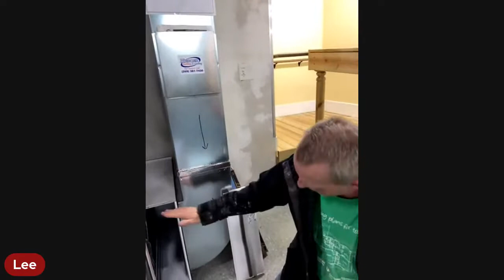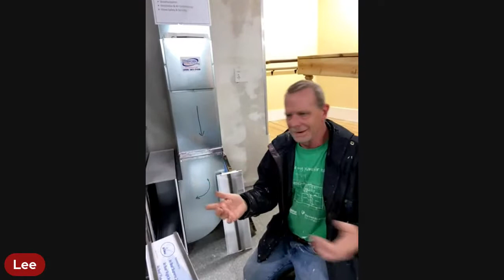The other thing is you want to make sure the filter is the correct size, not only thickness but also depth and height. I've seen it where somebody can't find the right size filter and just jams something in there, leaving a big gap on the back. All that dirty air flies by it and gets clogged into the squirrel cage, making it so the motor doesn't move as much air, which heats up the heat exchanger, which makes it conk out quicker or makes the furnace shut down because it's getting too hot. A lot of things boil down to your air filter.